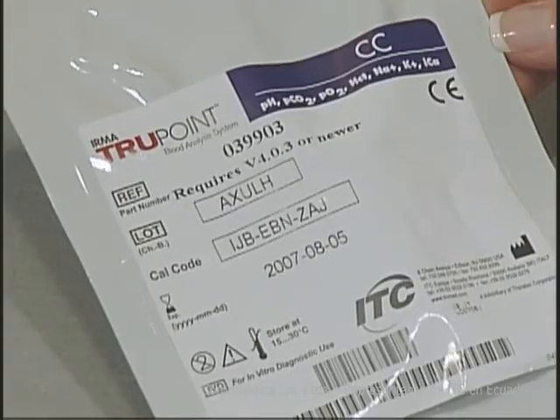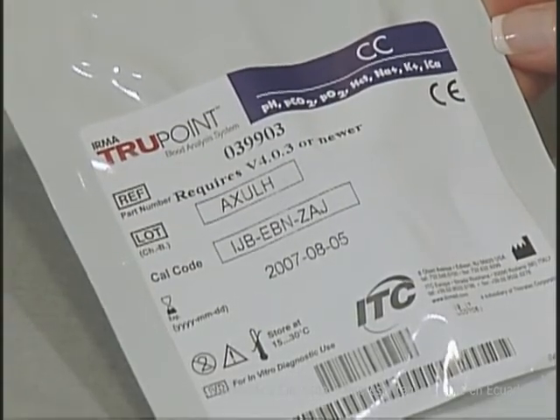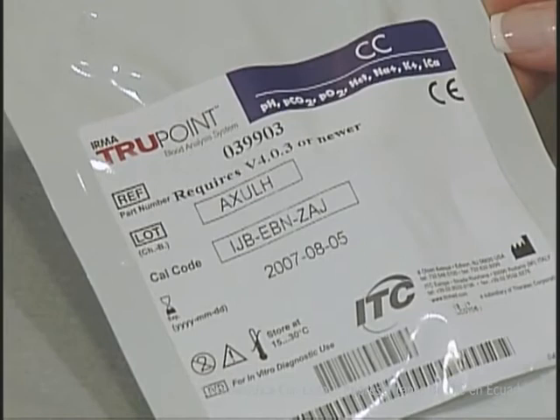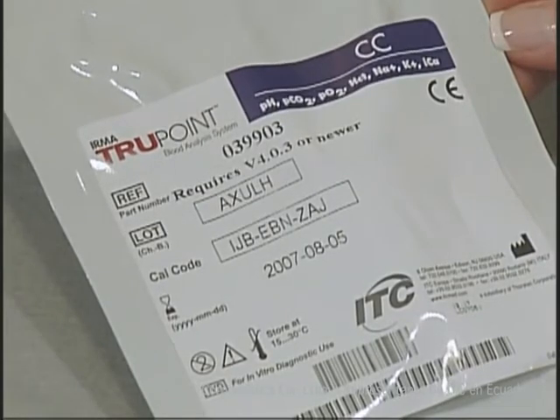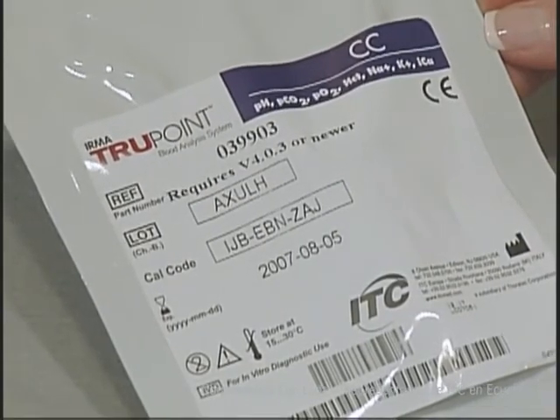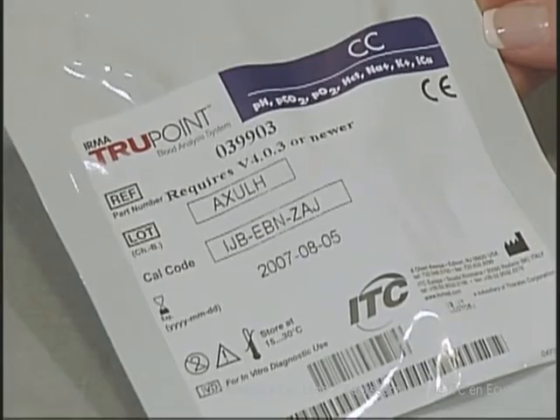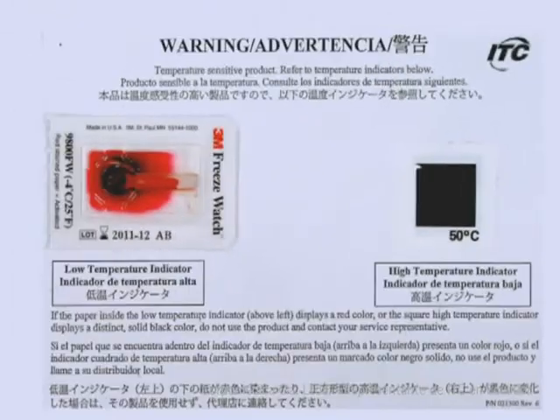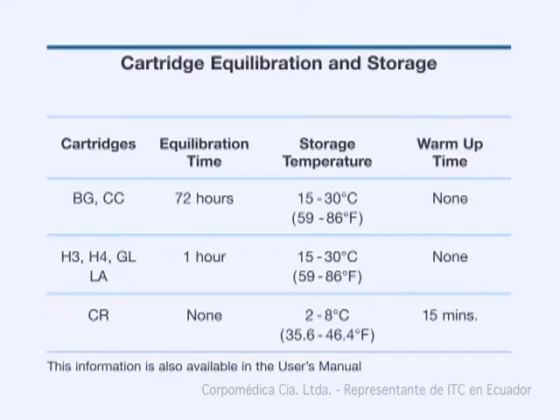Next, unpack the IRMA TruPoint cartridges from the insulated shipping container. Verify that the shipping temperature has stayed within the required range by making sure that the indicators have not been triggered. Do not use the cartridges if the indicators have been triggered. Here is an example of triggered indicators. To obtain accurate test performance, follow the recommendations for cartridge equilibration and store the cartridges in a stable environment away from air vents and sunlight. This information is also available in the user's manual.